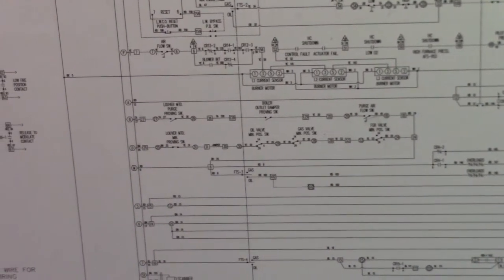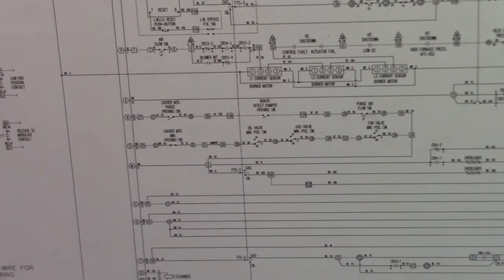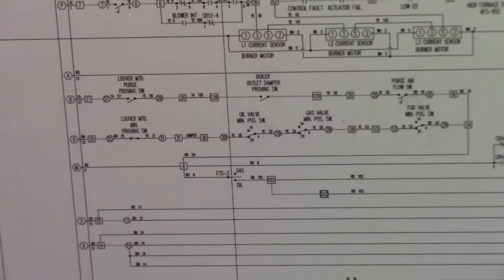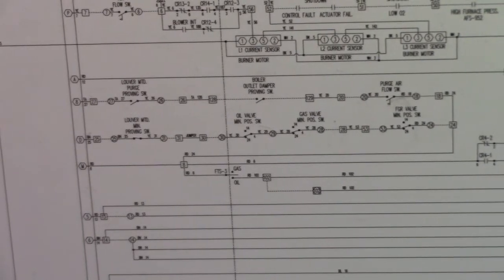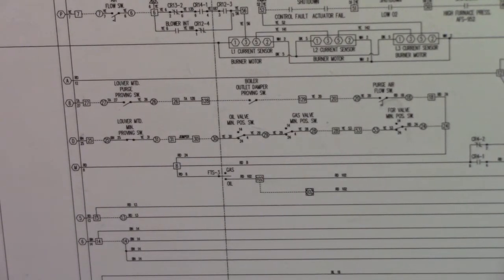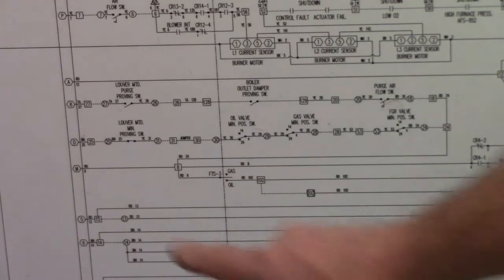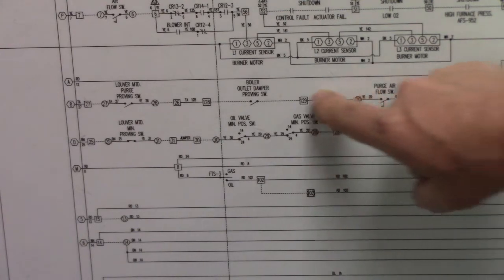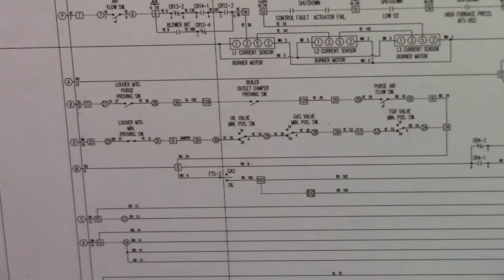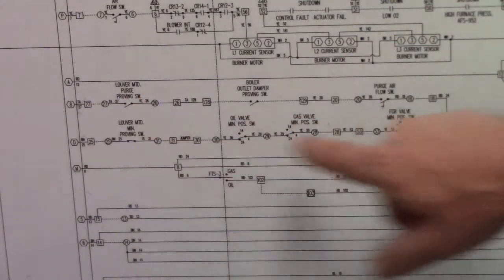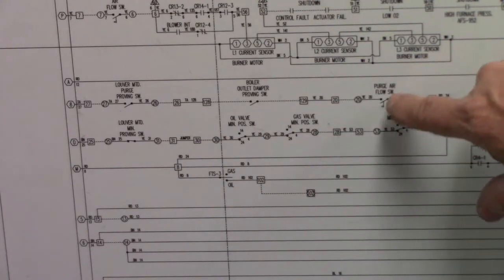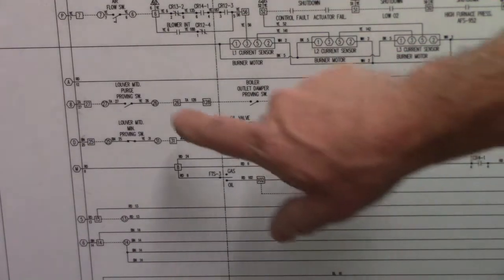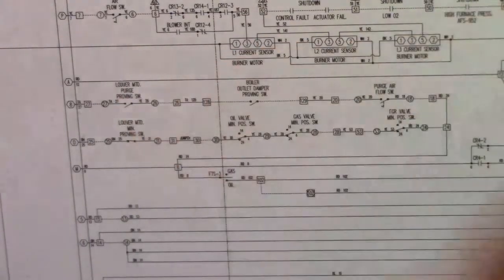And we see here the M8 loop. We see there are only three components in the loop: purge air flow switch, boiler outlet damper proving switch, and louver motor purge proving switch.